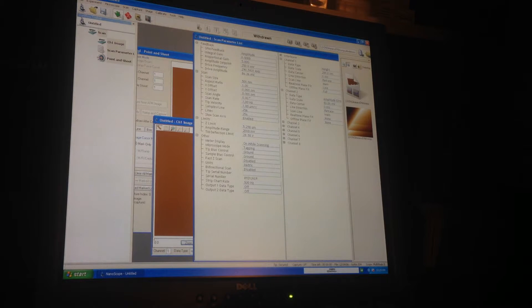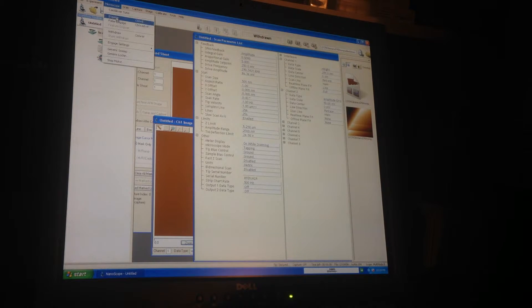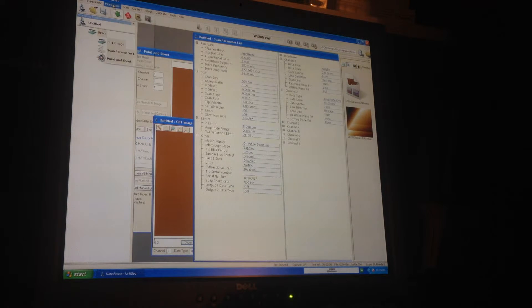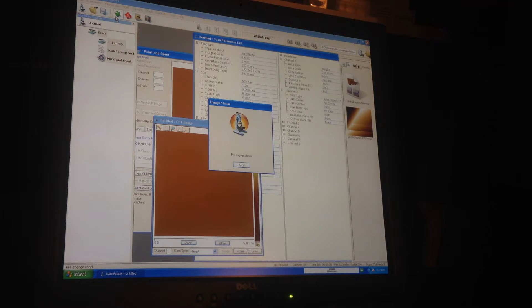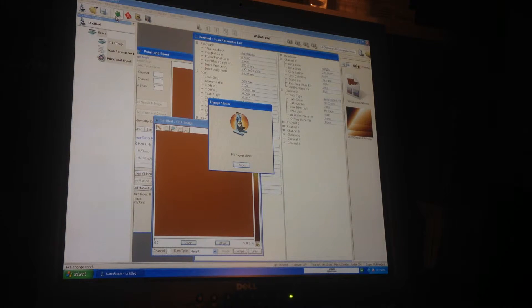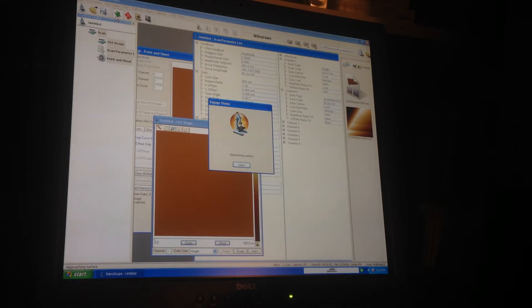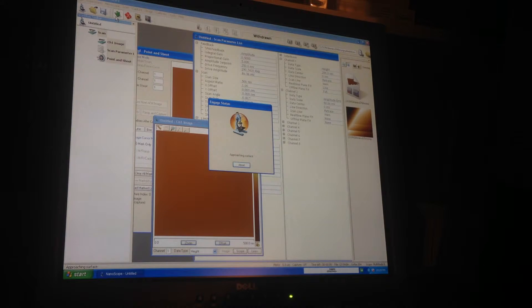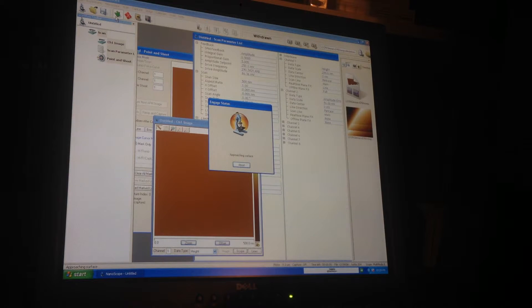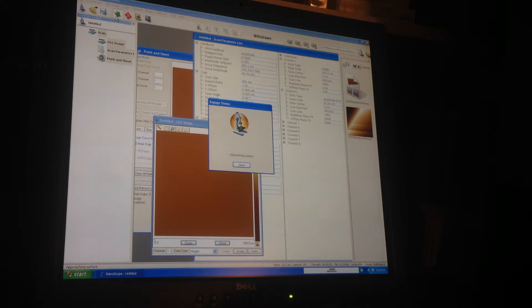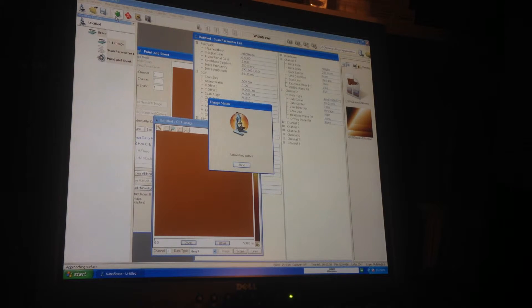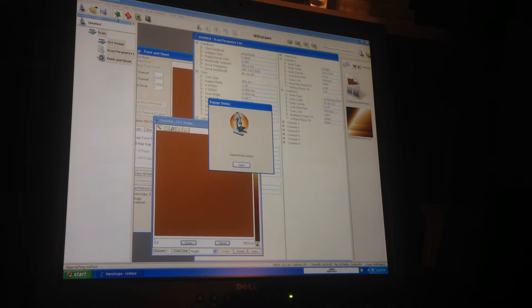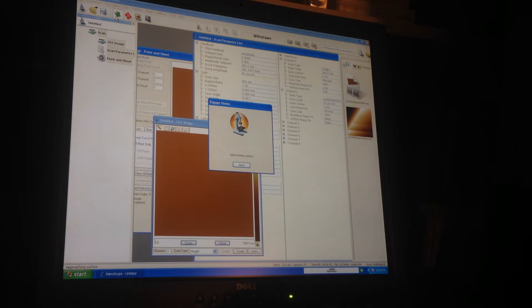Then you engage the tip - it says microscope engage. Now it should be far away from the surface, so this process would take a lot longer usually if you've just set up the cantilever, as it's taking longer to move the surface close to the cantilever. In this case, I withdrew the tip after having been engaged so it's a lot quicker.